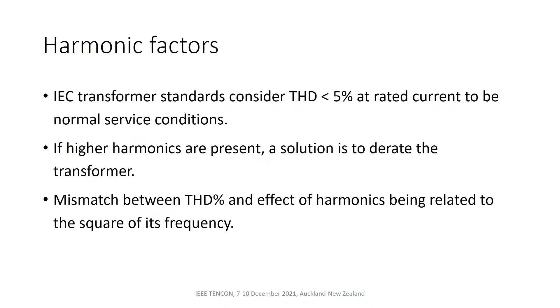But what we are concerned with is that in these transformer standards, if they're talking about the total harmonic distortion, then we can see there's a bit of a mismatch between that and the effect of the harmonics, because the total harmonic distortion does not consider the frequency, whereas the transformer does.